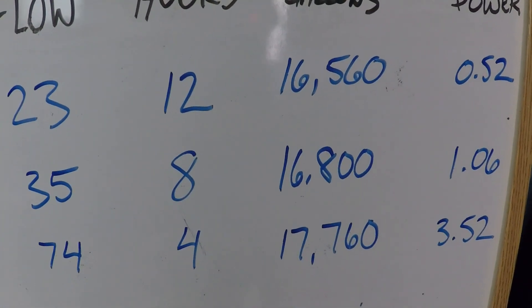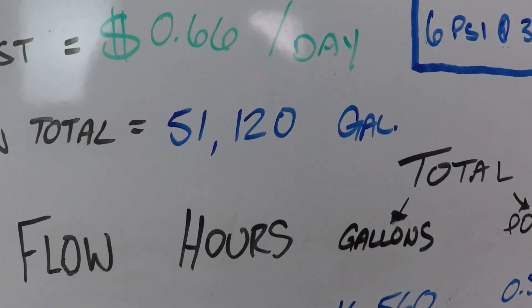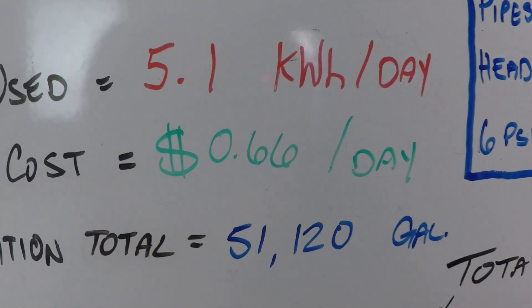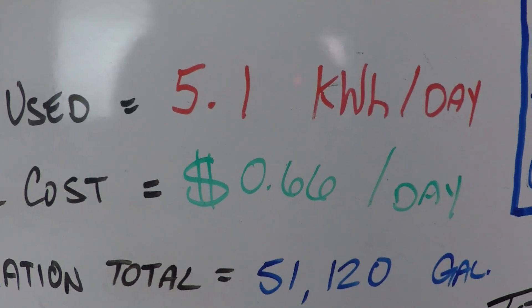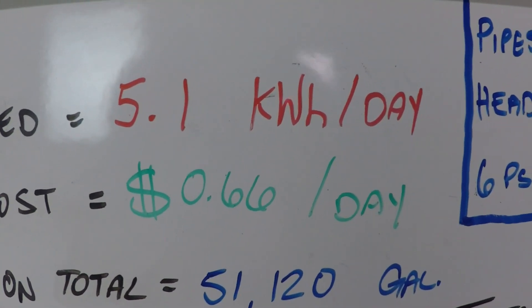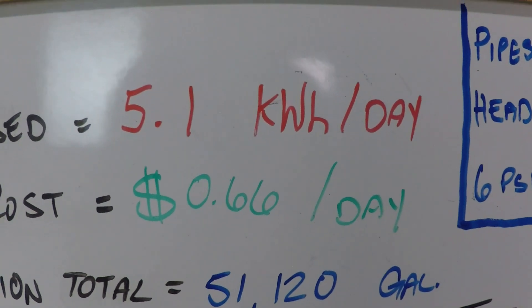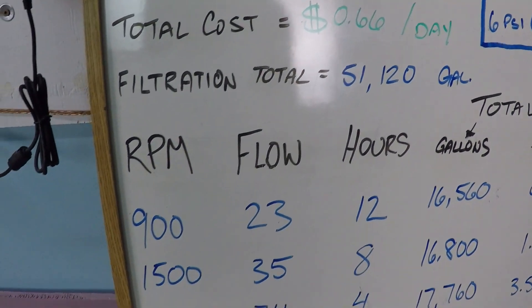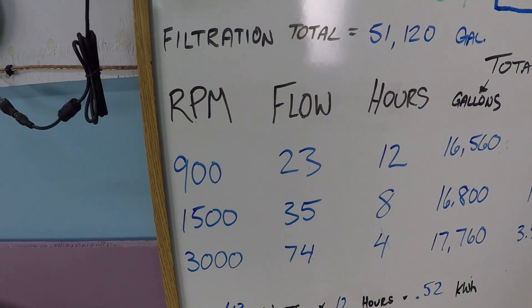The filtration totals will equal 51,120 gallons of filtered water every day, with 5.1 kilowatt hours of power consumed at a nationwide average of 13 cents per kilowatt hour. That is 66 cents per day to run this filtration schedule for 51,000 gallons of filtered water. Let's go ahead and look at some of these numbers now.